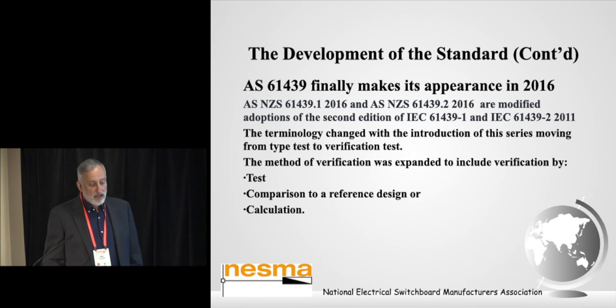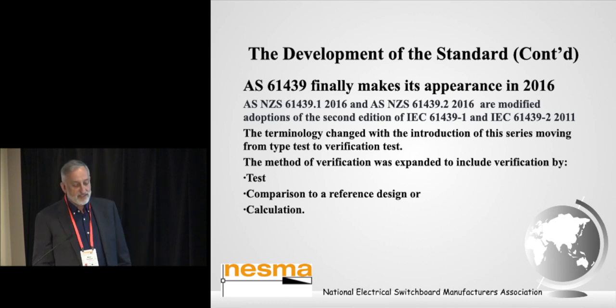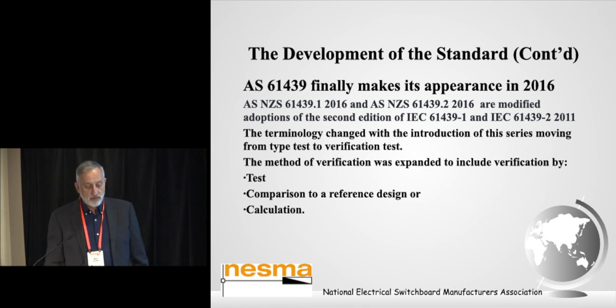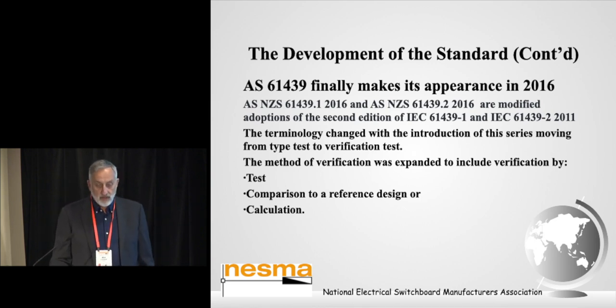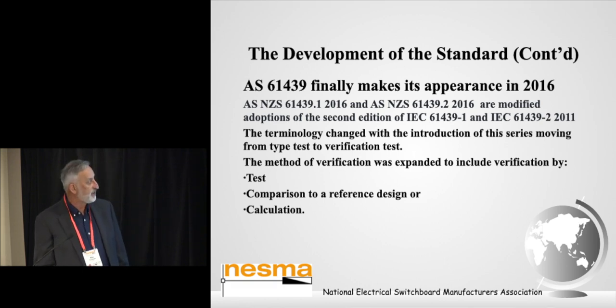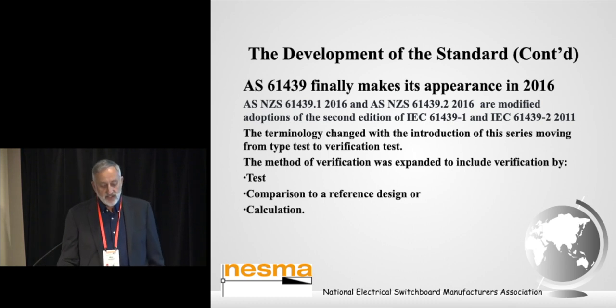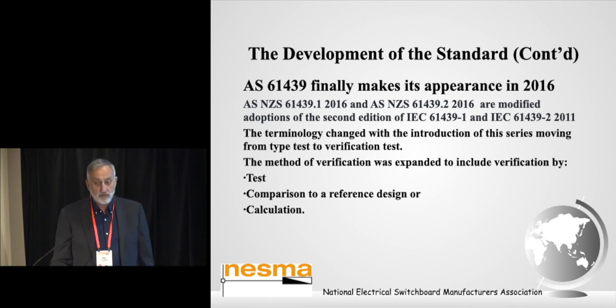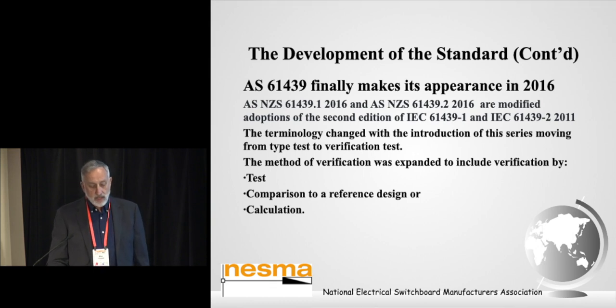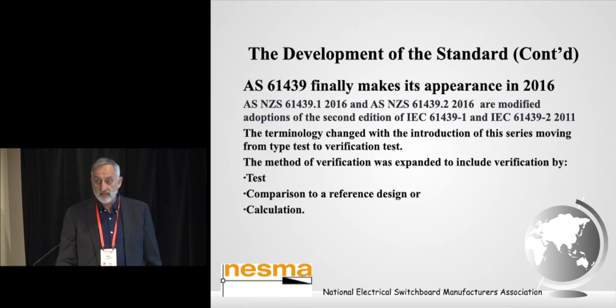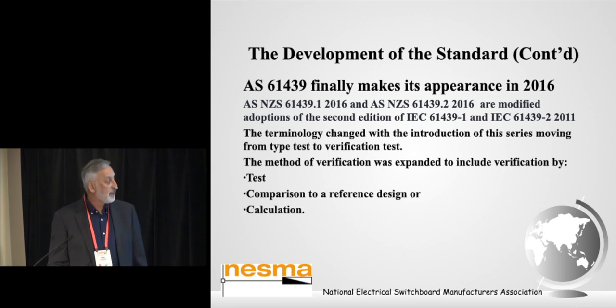So finally, in 2016, the Australian Committee adopts the 61439 series, so that's when we get AS 61439. And so we have Part 1 and Part 2, which are then modified adoptions of the second edition of the IEC document. The terminology changed with the introduction of this series, moving from type test to verification test. And the method of verification was expanded in this document to include verification by test, by comparison to a reference design, and by calculation.